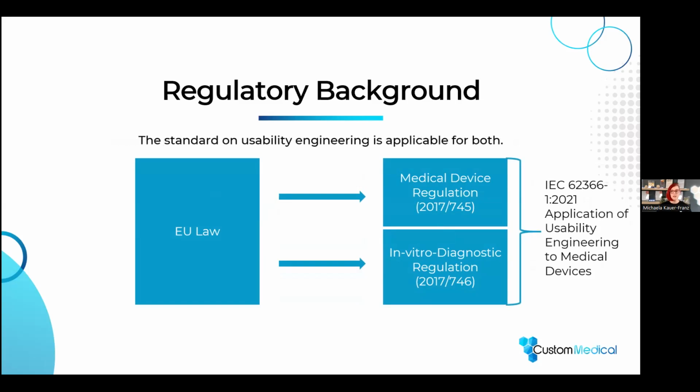And the standard, which is translating the requirements to you as a manufacturer, is the IEC 62366-1 in the newest version 2021. So it's called the Application of Usability Engineering to Medical Devices. This is the standard which is applicable even for the IVDs or IVDRs, because there is no single IVDR standard at the moment.